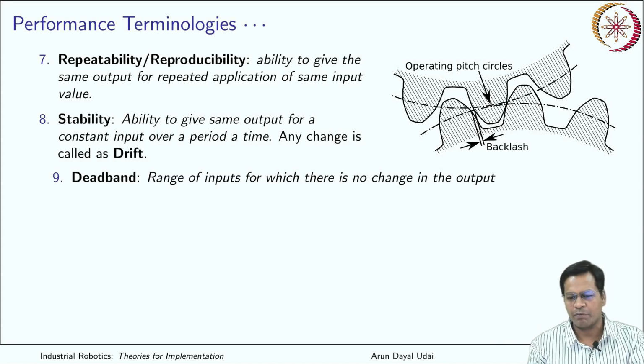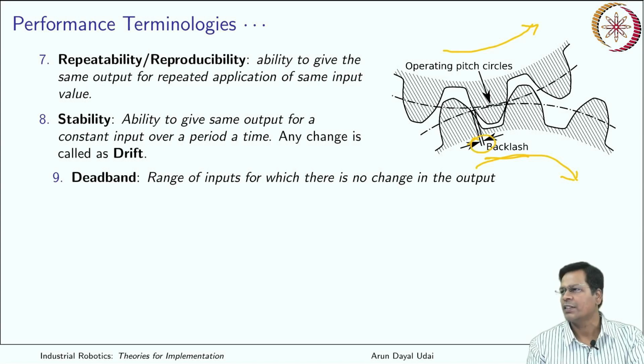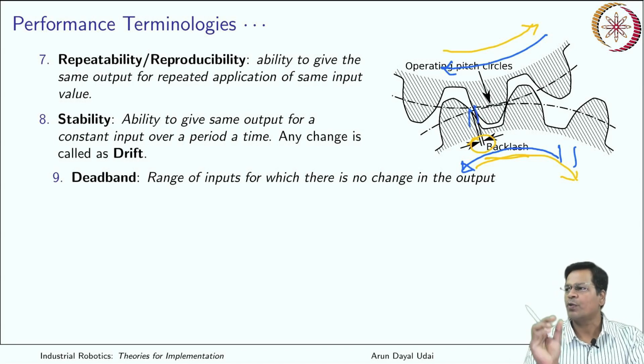Dead band is a range of inputs for which there is no change in output. It is very clearly explained by backlash in mechanical gears. If one gear is the driving one, the other is the driven gear. There is some clearance between them. If this is driving that, the clearance is on this side. So when it starts rotating in the opposite direction, the other gear will pick up, but only after a lag, after a period of time it takes to establish contact. Until then, the driven shaft does not move.